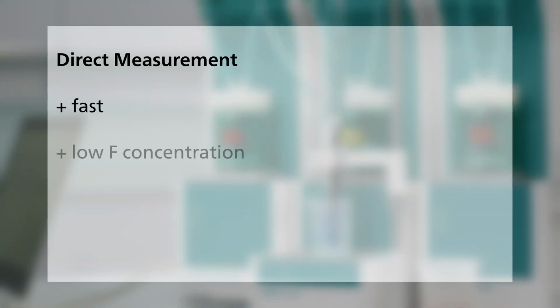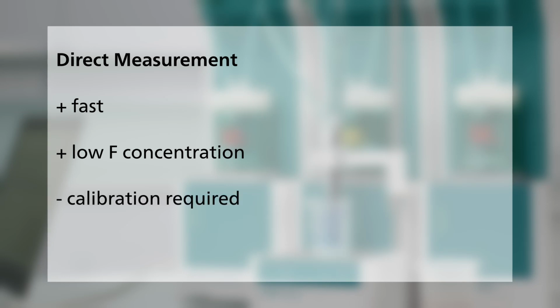Direct measurements are fast and suitable for lower fluoride concentrations. When performing direct measurements, a calibration is needed before each measurement series. Moreover, complex sample matrices can interfere with the analysis.